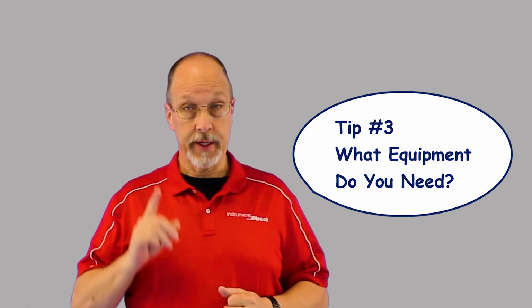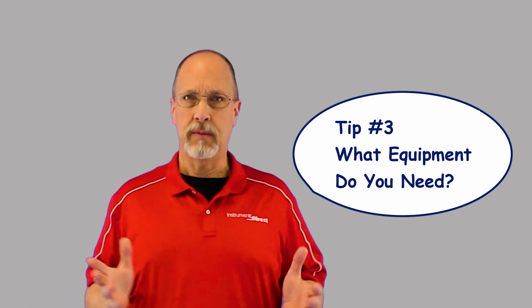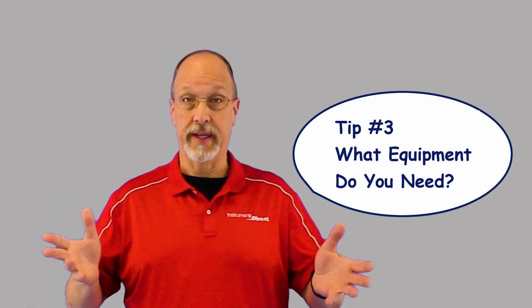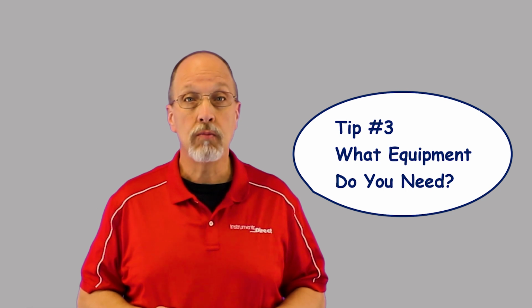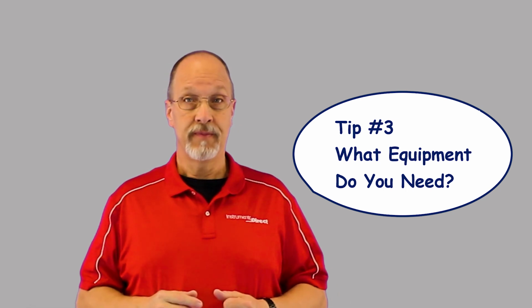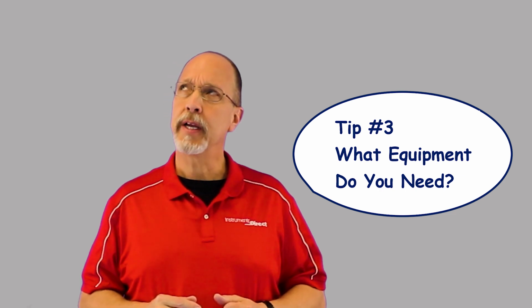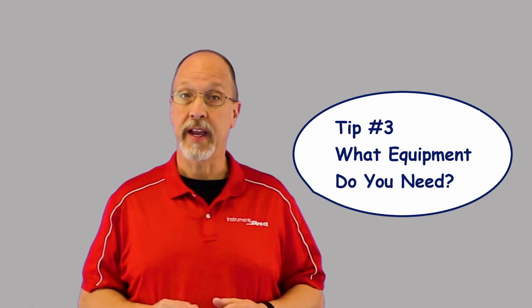Brings to mind tip number 3. What equipment do you need to conduct this flow survey? Well, that shouldn't be too hard. We already know our application and our data collection requirements, so we can select the appropriate flow meter. In this case, I need to monitor, let's say, a 10-inch carbon steel chilled water application for a week. So I selected a Fuji Portaflow Ultrasonic transit time flow meter with a data logger and a transducer for the 10-inch pipe application. Well, that's great if you own the equipment. If not, you'll just have to go out and buy it. Or since perhaps this is just a short-term requirement, why not just rent it?